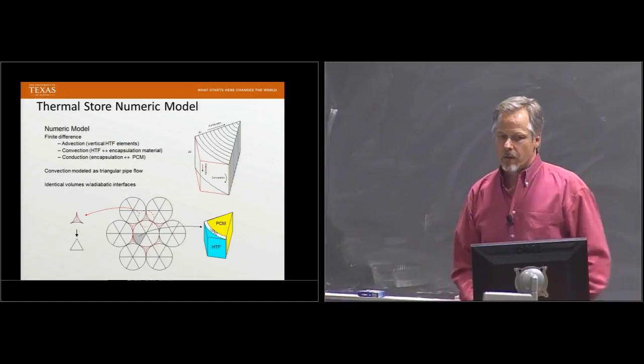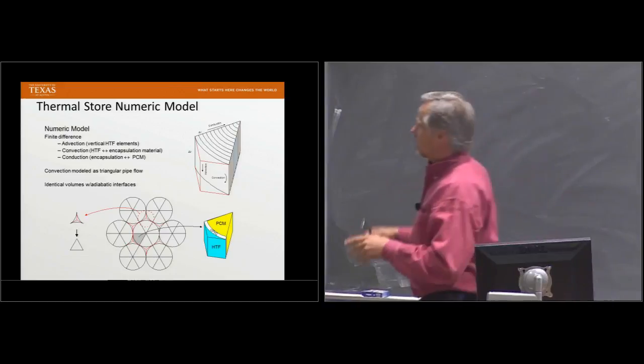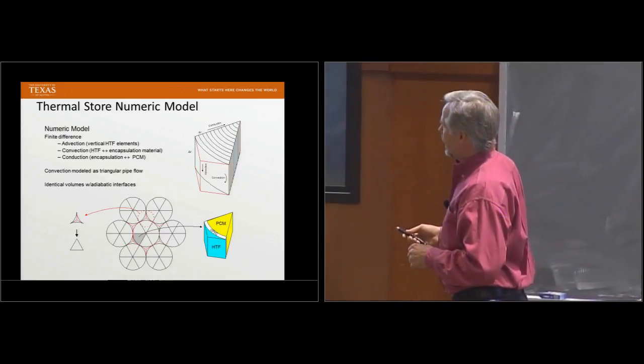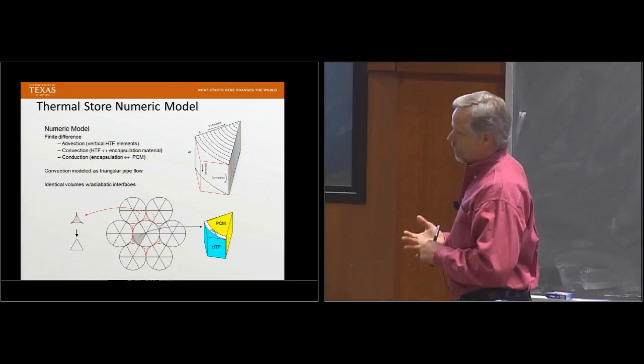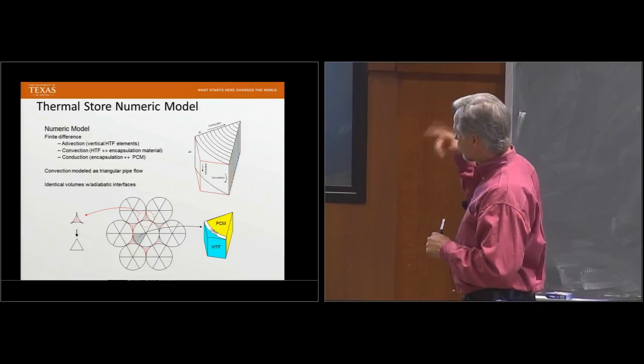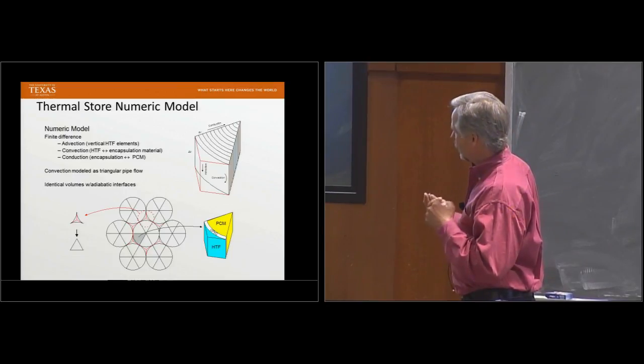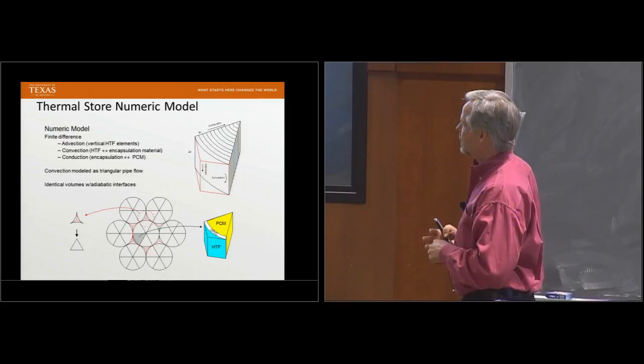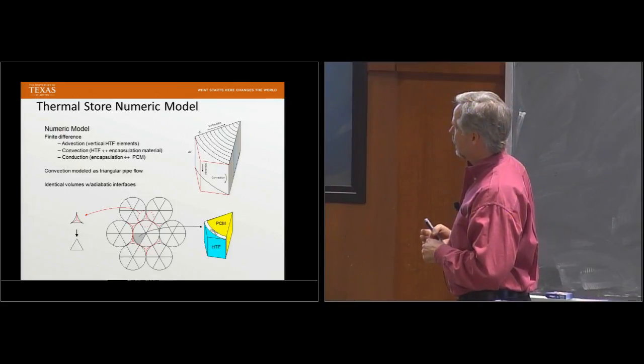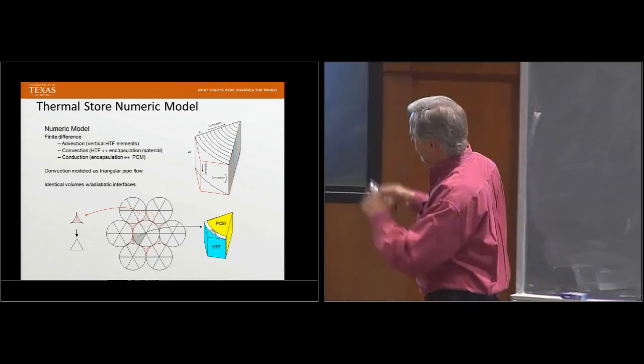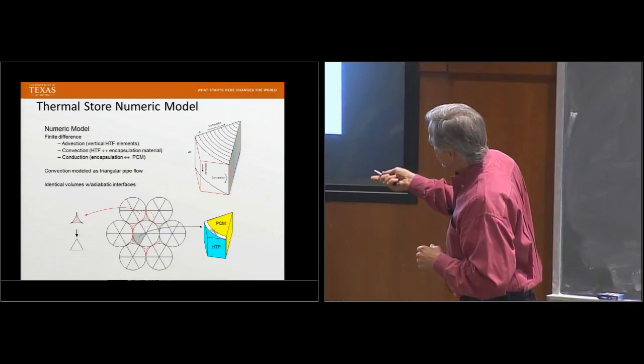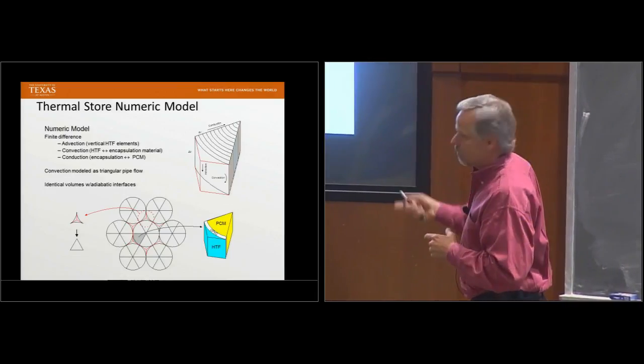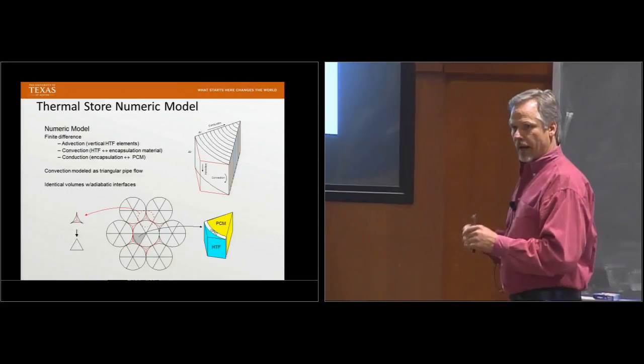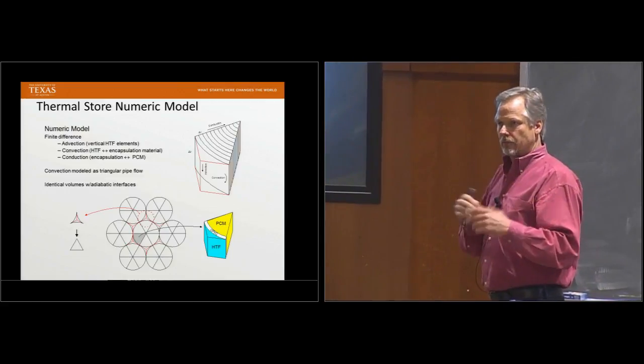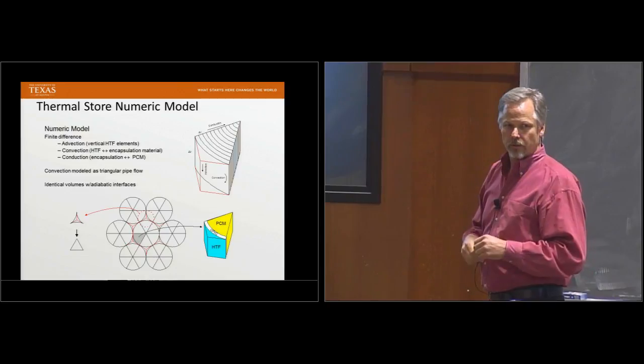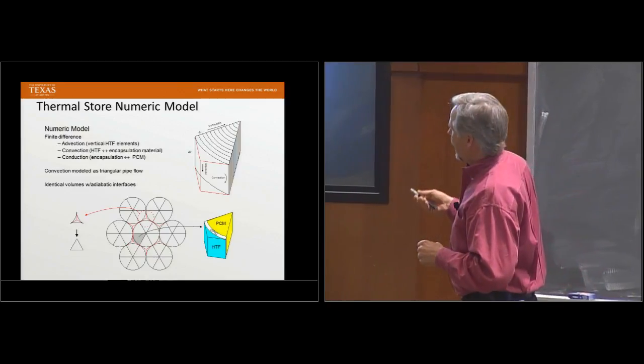So the numeric model, based on that design, deals with advection, convection, and conduction through the heat transfer fluid, the PVC shell, and the PCM thermal storage material. Because of the way these push together, we end up with these triangular shaped spaces. We're actually modeling those as triangular pipes. So it's just as if we're running fluid through a triangular pipe and doing heat transfer as a result. And that actually works out pretty well.